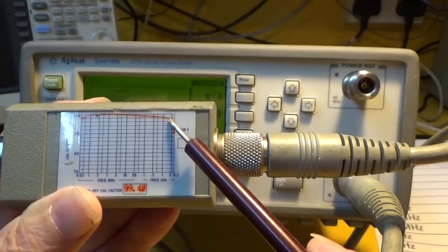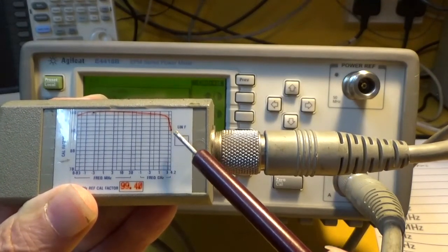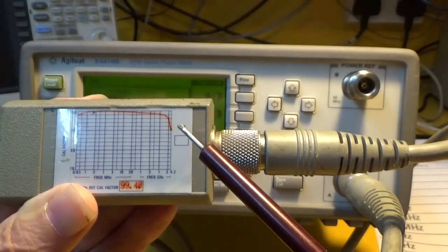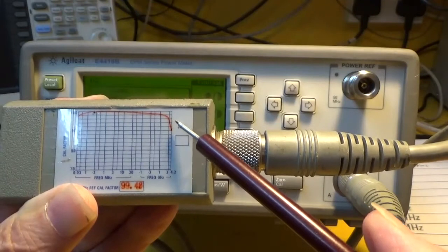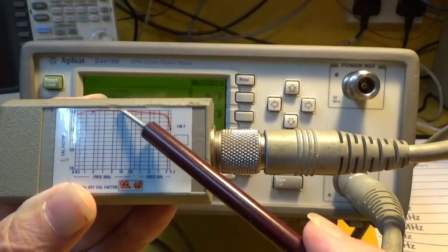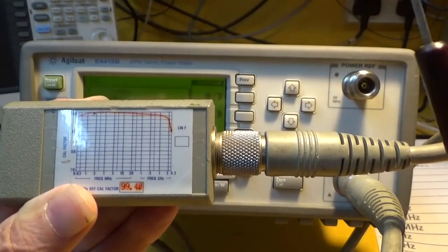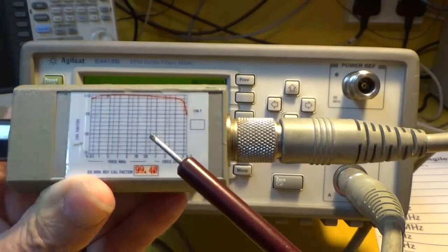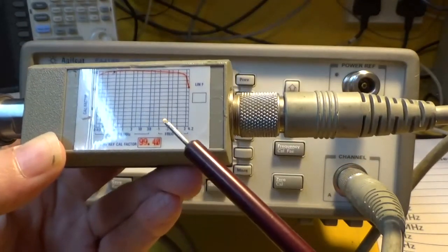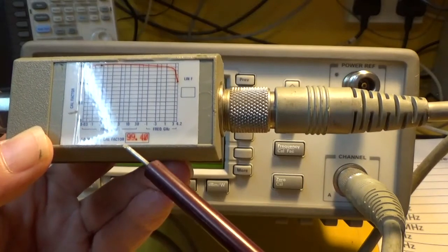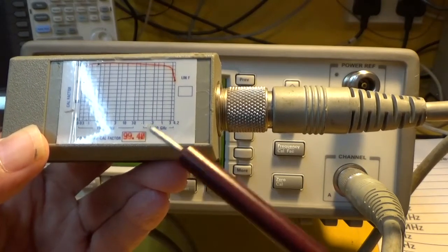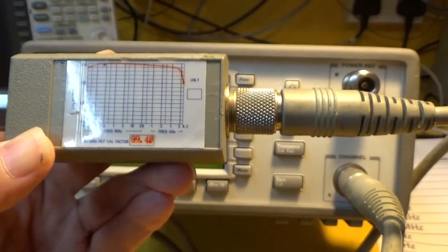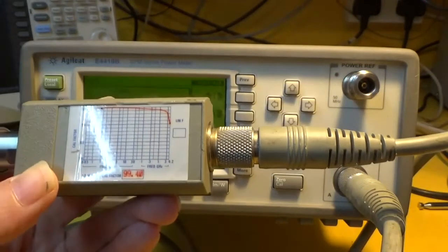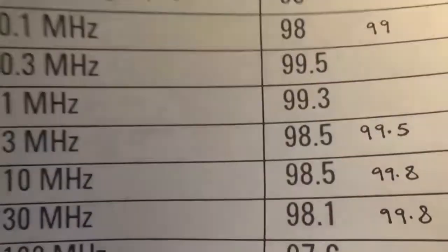As you get really high in frequency, you're dropping to 90% of the accuracy at its main frequency, lower frequency, whatever. But the standard reference point for calibrating these sensors, or calibrating your power meter, is at 50 megahertz, and at that frequency this has got a 99.4% correction, which you have to load into the meter you're using. As I said, they normally come with a printed table.